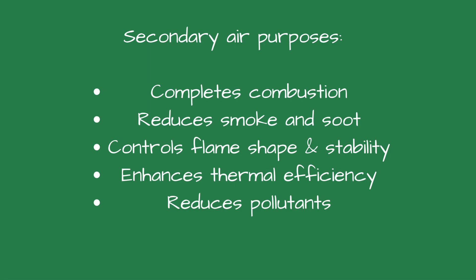Secondary air reduces carbon monoxide formation and improves efficiency. It reduces soot and smoke by enhancing combustion — minimizing soot, smoke, and particulate emissions, leading to a cleaner operation. Proper secondary air distribution helps shape and stabilize the flame, ensuring efficient heat transfer and reducing flame impingement on the boiler surfaces. You have more complete combustion, which means better fuel utilization, improving the boiler's efficiency and reducing costs. Lastly, adequate combustion air reduces the formation of harmful pollutants such as CO and unburned hydrocarbons, improving emissions compliance.